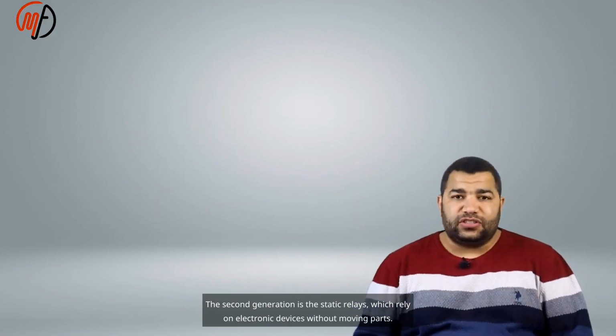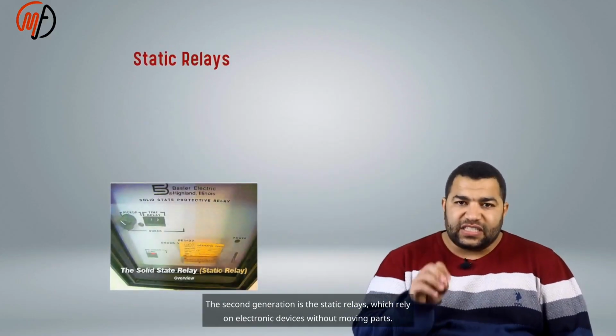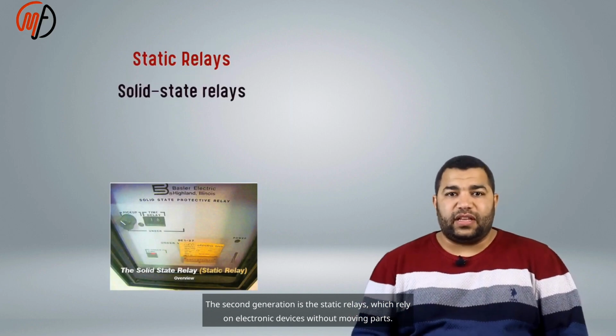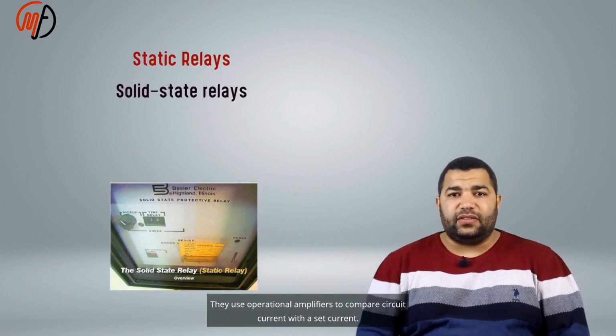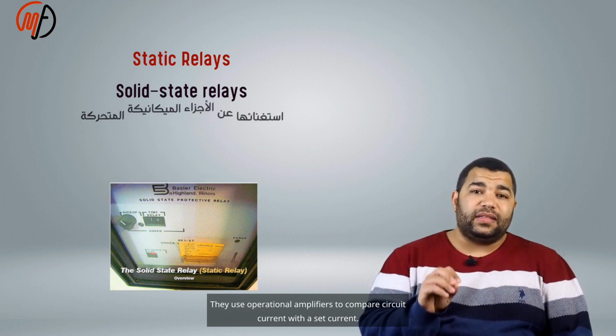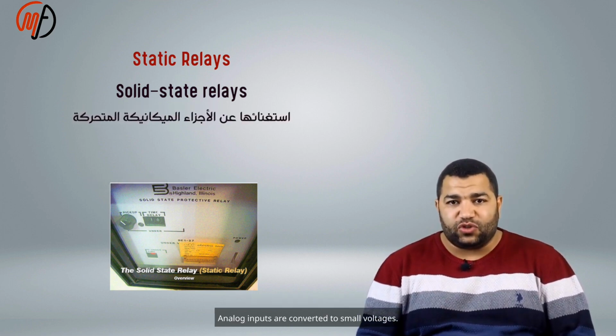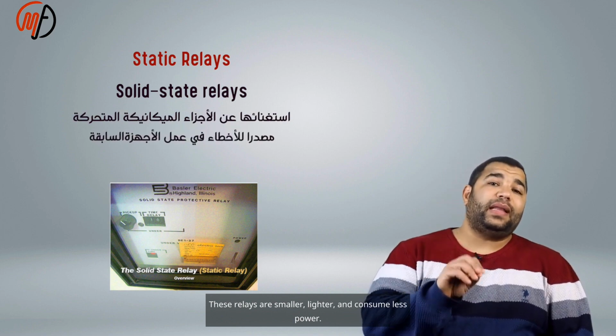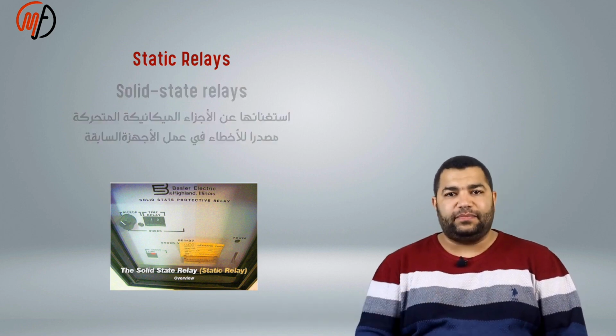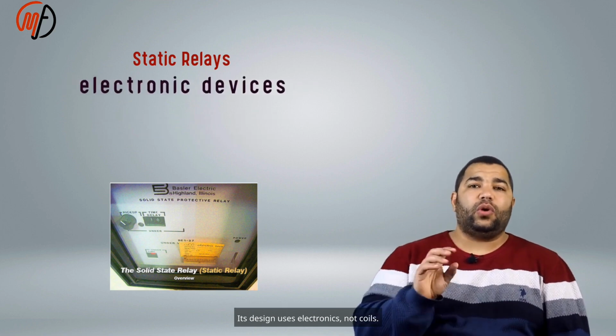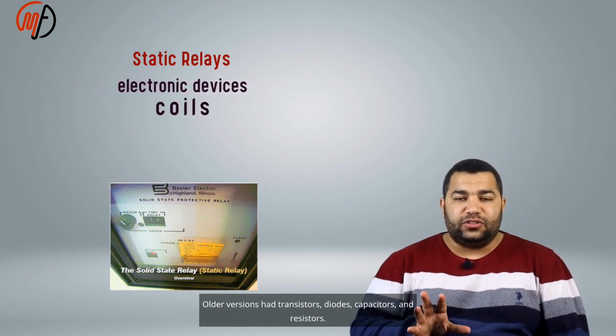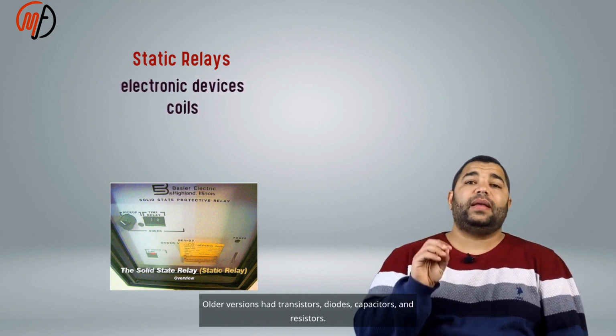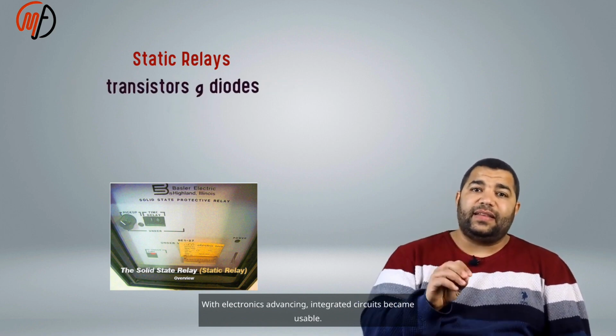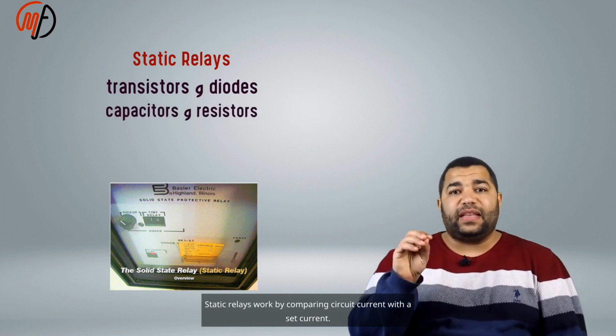The second generation is the static relays, which rely on electronic devices without moving parts. They use operational amplifiers to compare circuit current with a set current. Analog inputs are converted to small voltages. These relays are smaller, lighter, and consume less power. Its design uses electronics, not coils. Older versions had transistors, diodes, capacitors, and resistors. With electronics advancing, integrated circuits became usable.